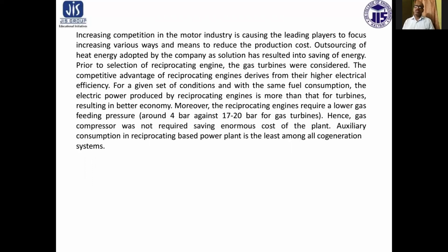Increasing competition in the motor industry is causing the leading players to focus on various ways and means to reduce production cost. Outsourcing of heat energy, adopted by the company as a solution, has resulted in savings of energy. Prior to selection of the reciprocating engine, gas turbines were considered. The competitive advantage of reciprocating engines derives from their higher electrical efficiency for a given set of conditions and with the same fuel consumption. The electric power produced by a reciprocating engine is more than that of a turbine, resulting in better economy. Moreover, the reciprocating engine requires lower gas feeding pressure, around 4 bar against 17 to 20 bar for gas turbines. Hence a gas compressor was not required, saving enormous cost of the plant.